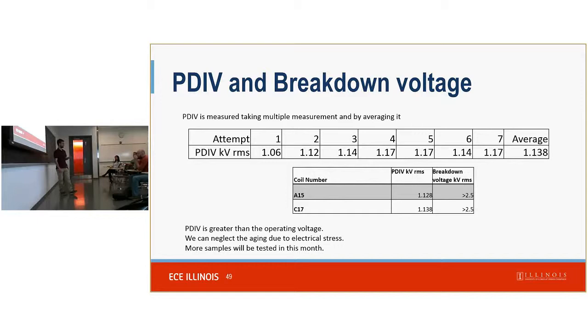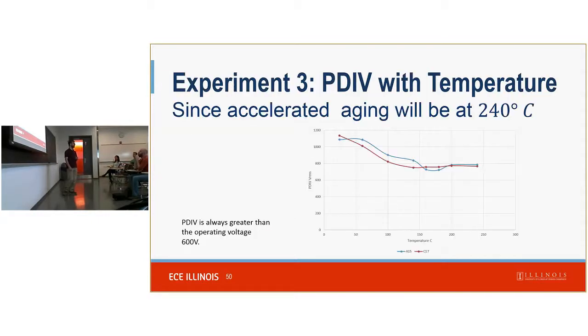This is showing the average across multiple trials was about 1.1 kV for partial discharge inception voltage, which is above the operating point, and partial discharge is not catastrophic failure. So it's okay to occasionally have some partial discharge. We also demonstrated that the partial discharge inception voltage decreased at increasing temperatures, which is to be expected. But it's important to understand because the operating temperature of our machine is expected to be quite a bit higher than room temperature, at 200 C, or just above 200 C.